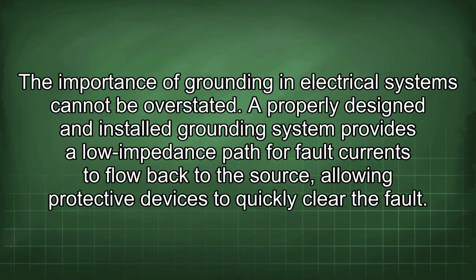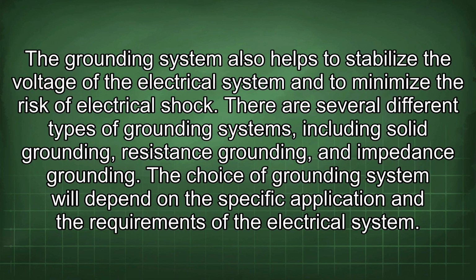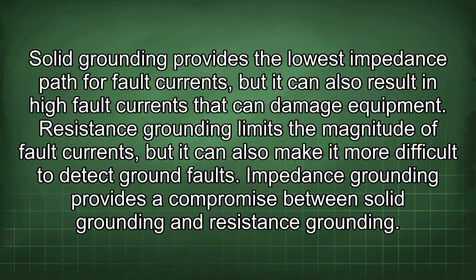A properly designed and installed grounding system provides a low impedance path for fault currents to flow back to the source, allowing protective devices to quickly clear the fault. The grounding system also helps to stabilize the voltage of the electrical system and to minimize the risk of electrical shock. There are several different types of grounding systems, including solid grounding, resistance grounding, and impedance grounding. The choice of grounding system will depend on the specific application and the requirements of the electrical system. Solid grounding provides the lowest impedance path for fault currents, but it can also result in high fault currents that can damage equipment. Resistance grounding limits the magnitude of fault currents, but it can also make it more difficult to detect ground faults. Impedance grounding provides a compromise between solid grounding and resistance grounding.